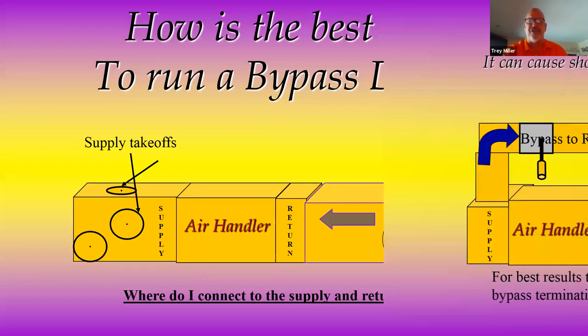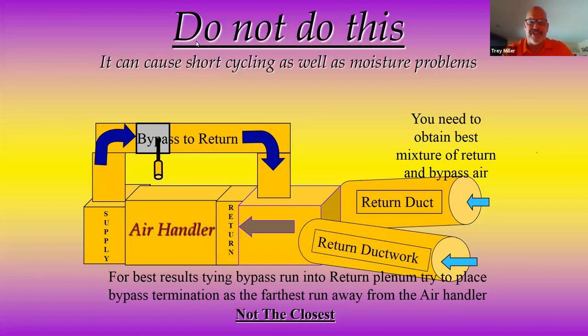And this is what you used to see all the time, and it says, do not do this. Well, gentlemen, let me tell you, with a barometric weighted arm bypass, if it's already installed with this type of ductwork, with the bypass tied in at the beginning of the plenum, the majority of my return static is at the first takeoff. So I don't want that. But from a retrofit standpoint, the neat thing is, gentlemen, pull this barometric bypass off, put in a smart bypass, and I've had guys telling me all over my territory, this simple little solution takes care of the problem.